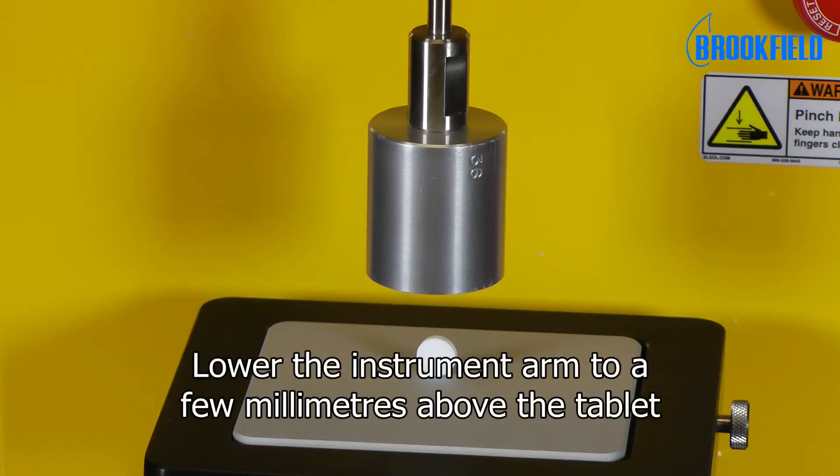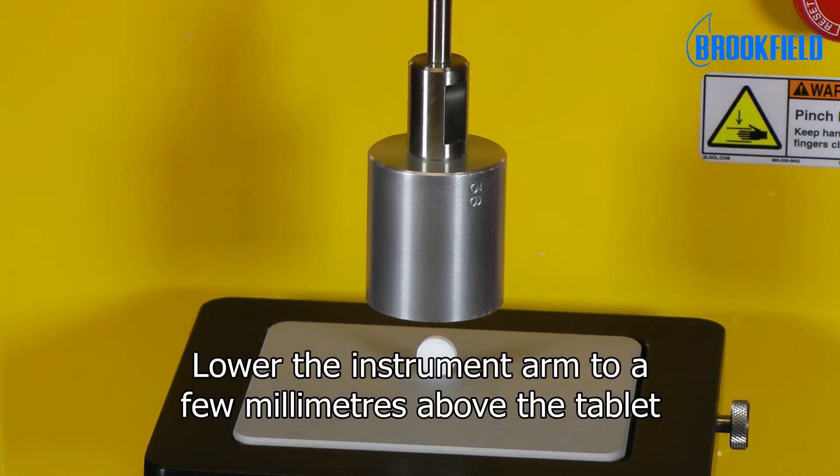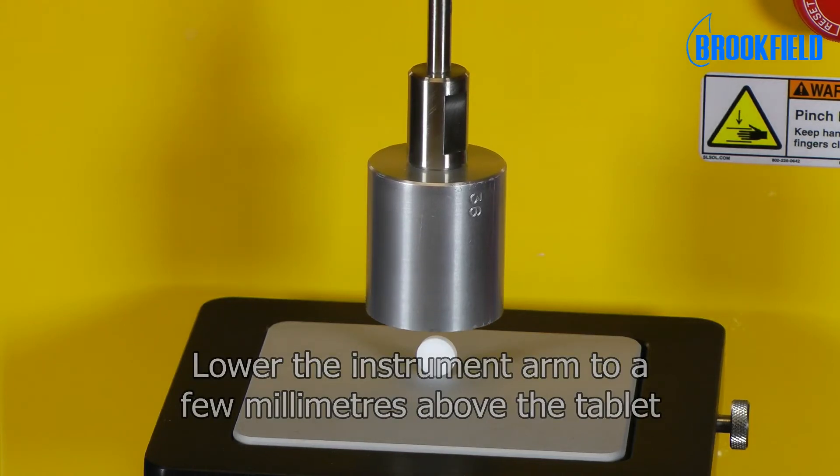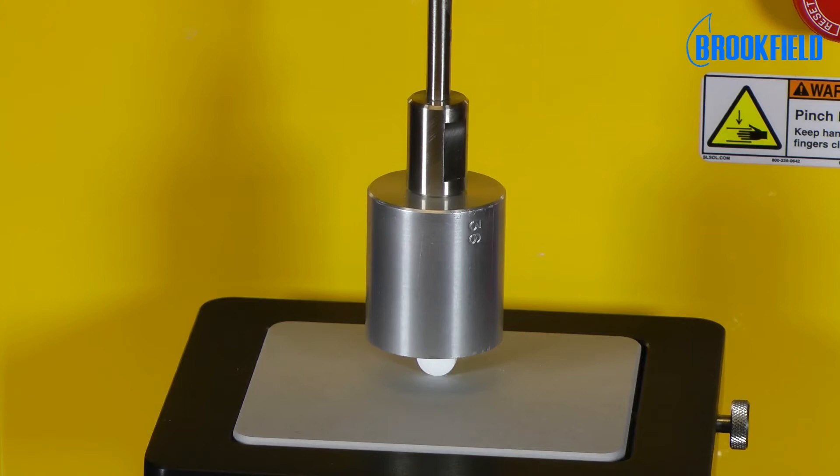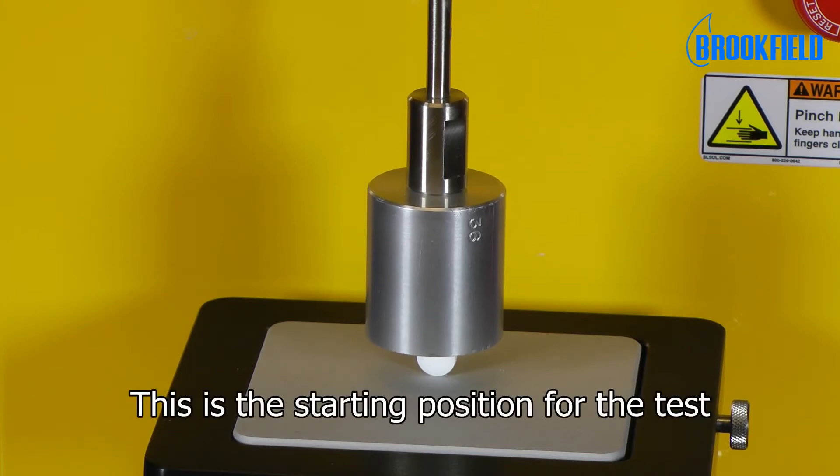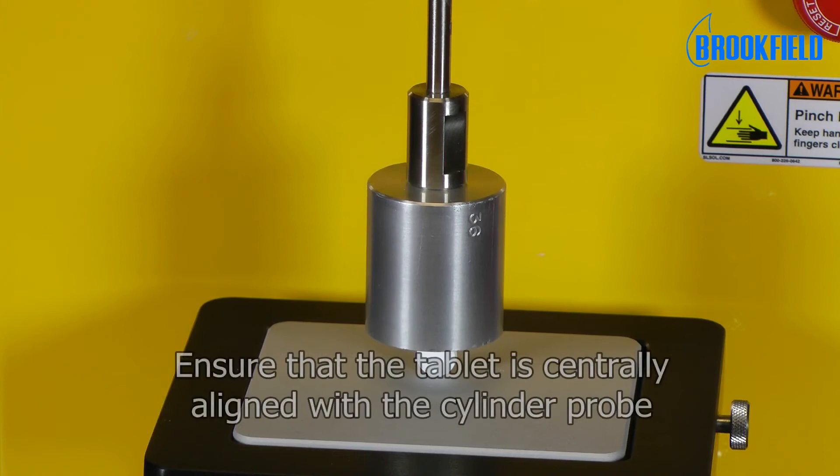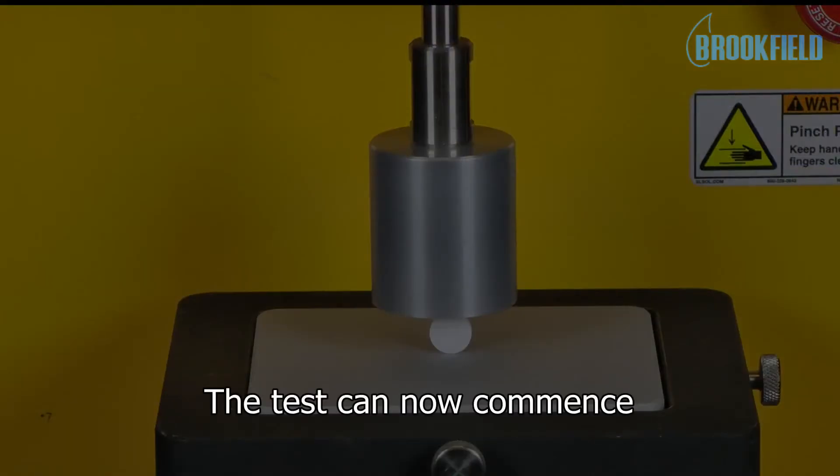To ensure that the tablet is centrally under the probe, lower the instrument arm to a few millimeters from the tablet surface. This can be the starting position for the test. Ensure that the tablet is centrally aligned under the probe. The test is now ready to begin.